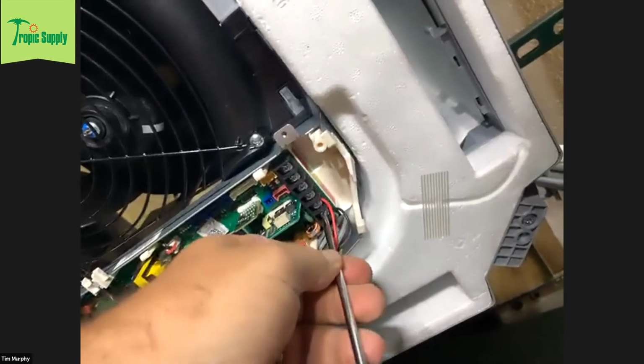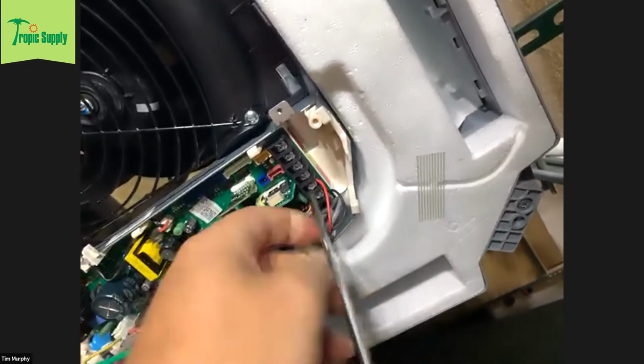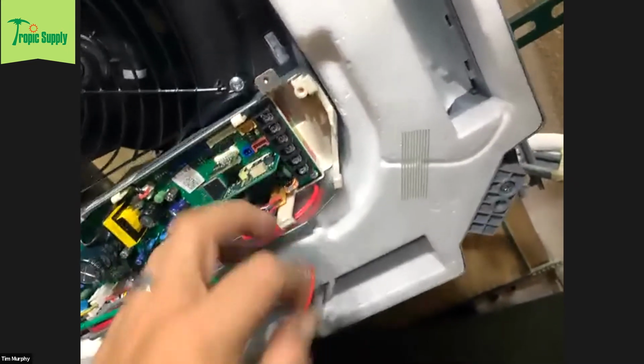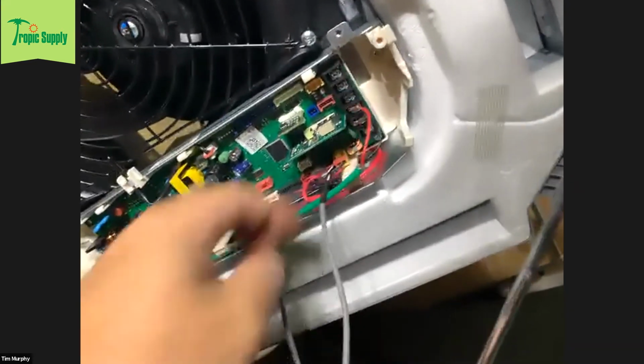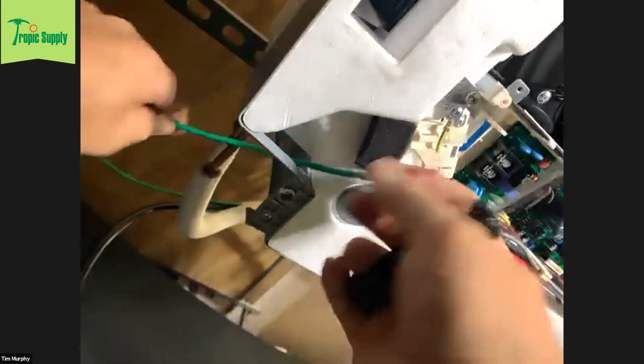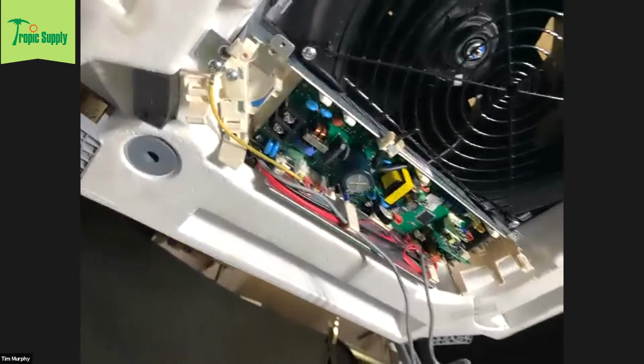Just want to make sure we're clear that it's 14 gauge wire for the high voltage, but you must use a separate 16-2 shielded stranded wire for communication. You cannot run the communication through the 14 gauge high voltage wire like some of our competitors do. Correct. These systems need that shielded wire.